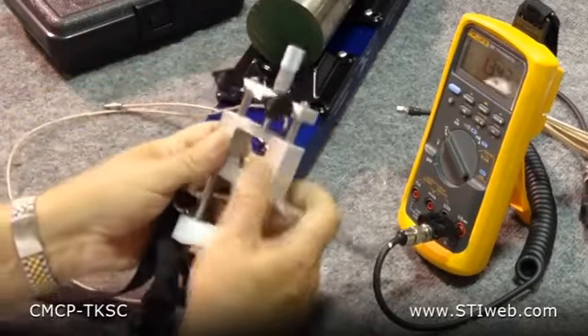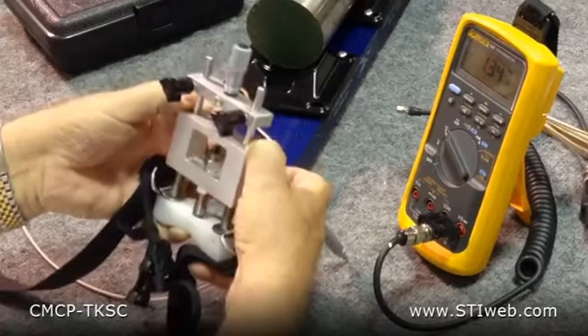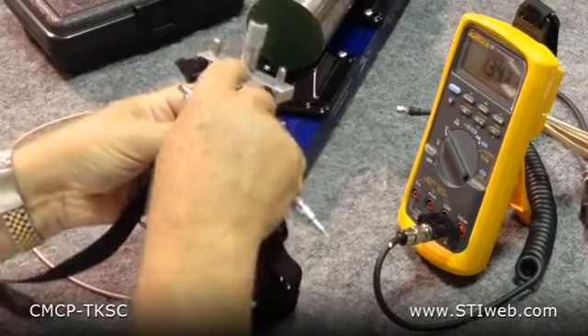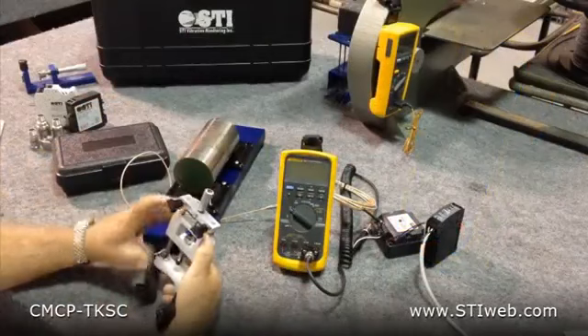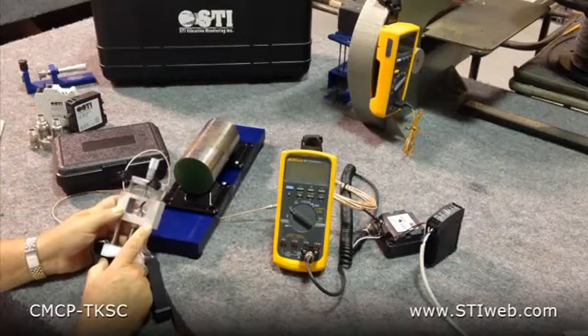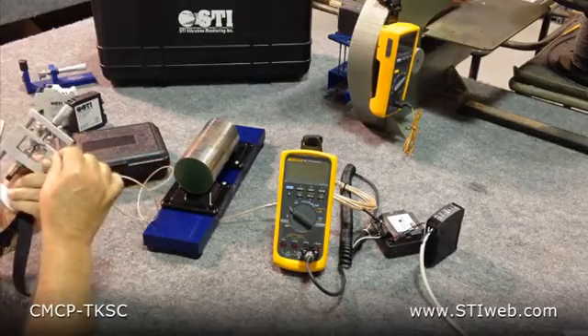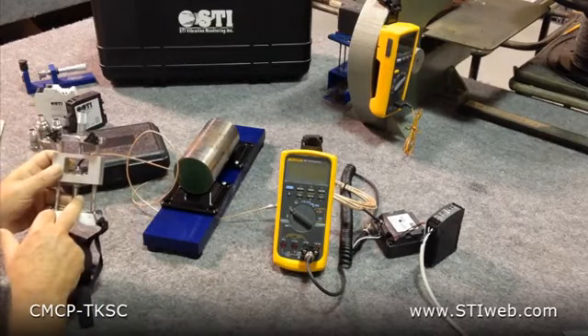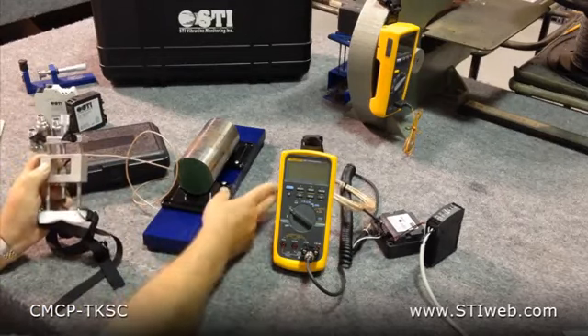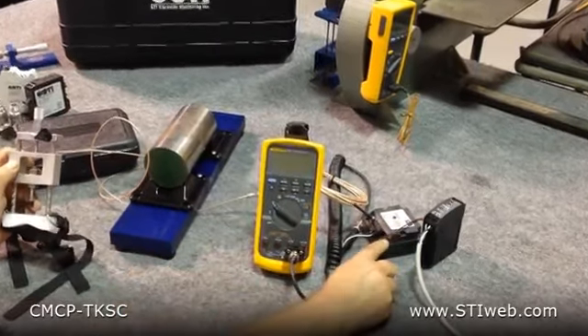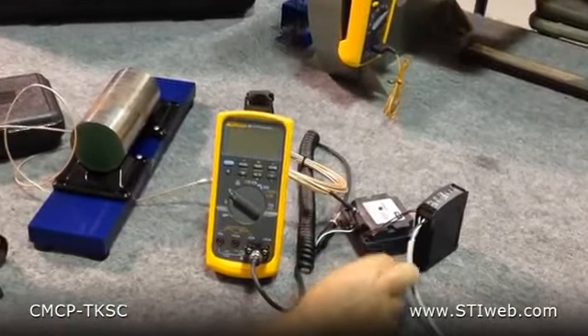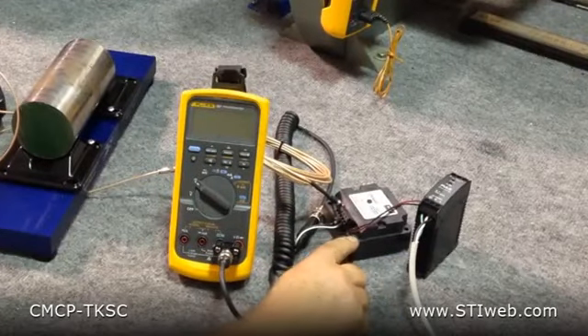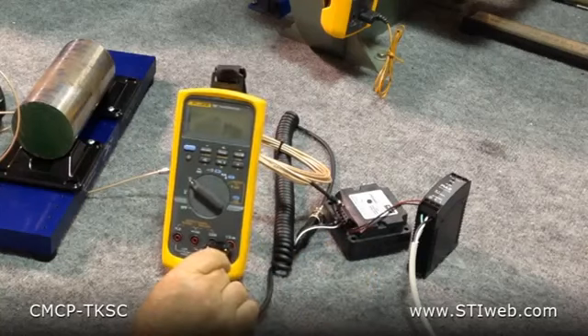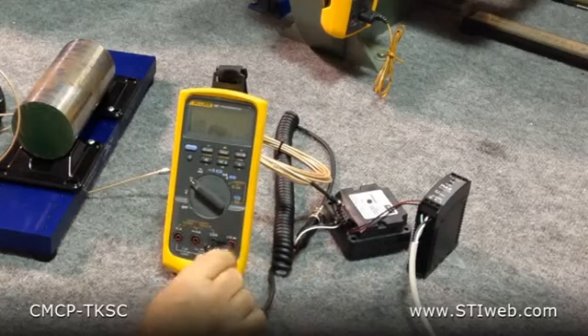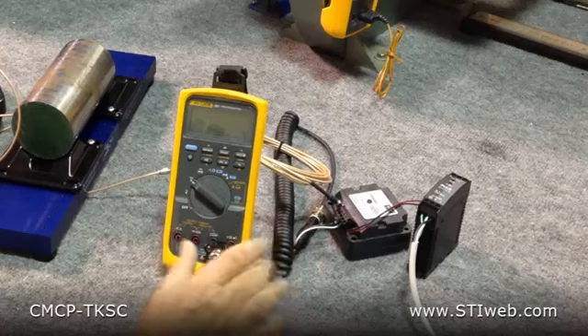So basically the armature is spring-loaded, and the top plate holds it so you can zero the micrometer out. The test setup is going to be made up of the TKSC, a proximity probe system with the probe mounted in the armature. The proximity probe system is wired to the extension cable, to the proximeter or driver as some call it, and of course you need a power source for this driver. Then the driver output we're going to wire to a digital voltmeter, where we're going to measure the negative volts DC coming out of the driver based on gap.